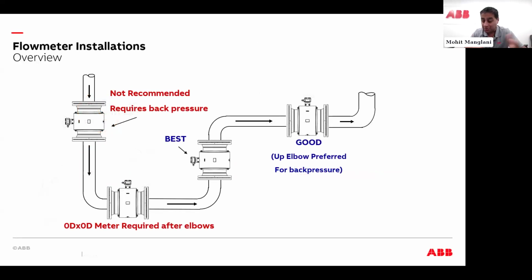So this is, like I said, for those that have met me or if I've done a presentation for you before, you may have seen this slide. If you look at this meter over here, if you have flow coming down all the way on the left, the risk of this installation is there's no guarantee that you're going to have a full pipe. That mag meter might give you issues or a noisy output. If you're right around a bend, you need a specialized mag meter, a 0Dx0D mag meter, which Allied ABB does have. The best installation, as mentioned before, is vertical up. You're going against gravity. You're always guaranteed a full pipe. And then obviously, if you're going on top of a bend, as long as you have enough upstream and downstream piping, you'll be able to accommodate good accuracy for the meter itself.